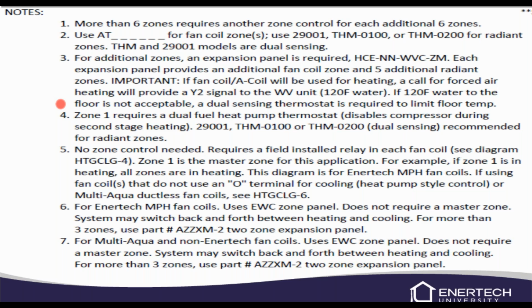If you've only got air handlers, just call us in tech support, and we'll discuss with you what may be your best setup. If you're going to use the MPH fan coils, we can use the EWC zone panel. And with the EWC, it's not going to require a master zone, and the system can switch back and forth from heating to cooling. On the EWC, it can handle up to 3 zones. There are 4 zones available on an EWC zone panel, but one of those zones is going to be a dummy.